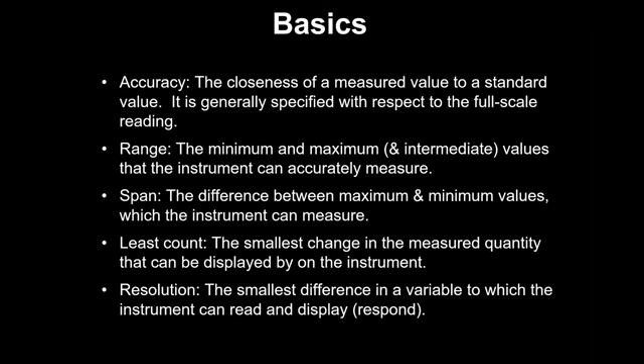Many of the thermocouples, the accuracy is 1%. And mind you, the accuracy is generally defined as a percentage of full scale reading. So when you say that the instrument can measure 0 to 600, that means the full scale reading is 600. Now, if you take 0.25% of 600, it comes to 1.5. So that means whatever reading they were taking, it could be wrong by 1.5 degree on either side. So in this particular case, the reading was 9. So that means the temperature could have been anything from 10.5 to 7.5, because that is the accuracy of the instrument.